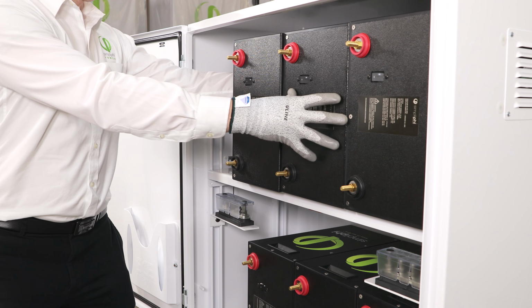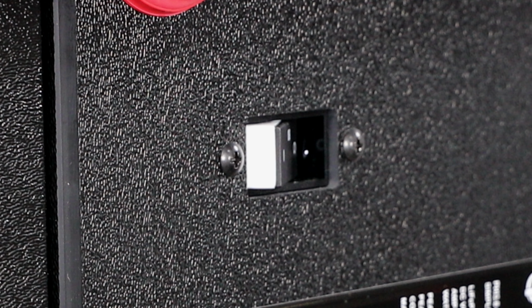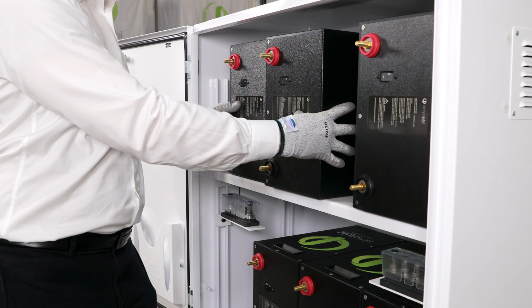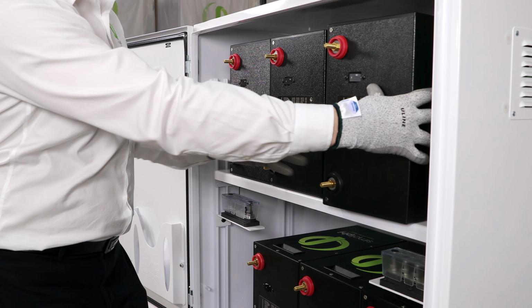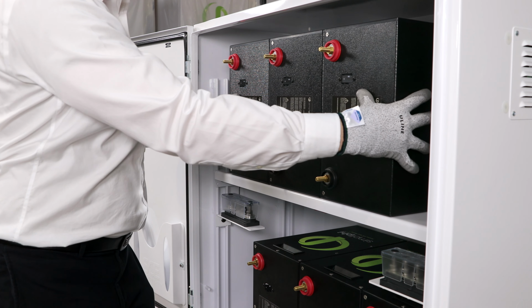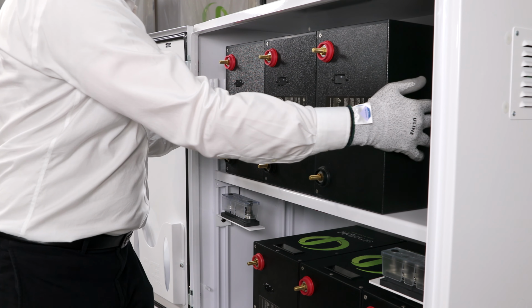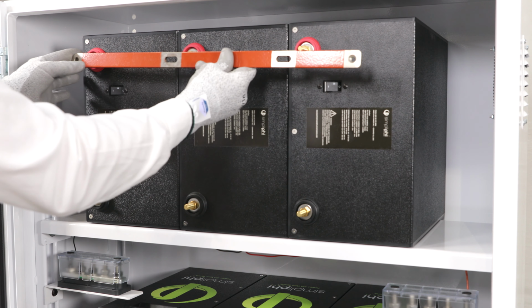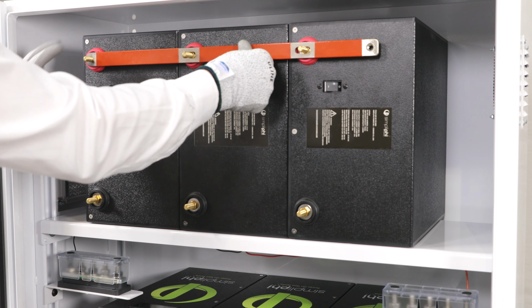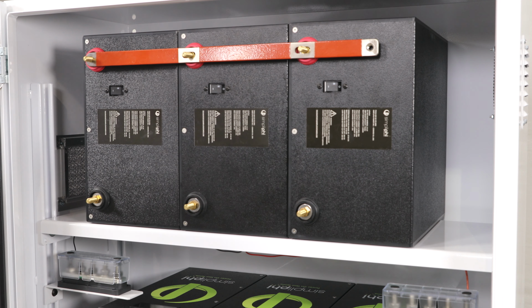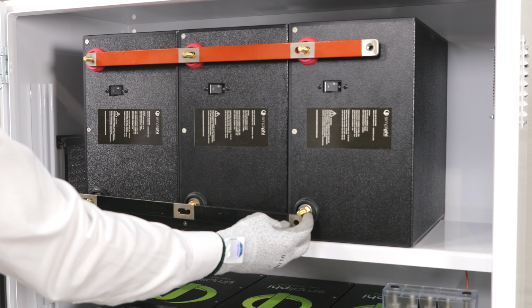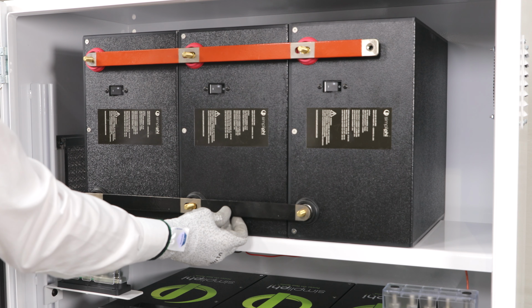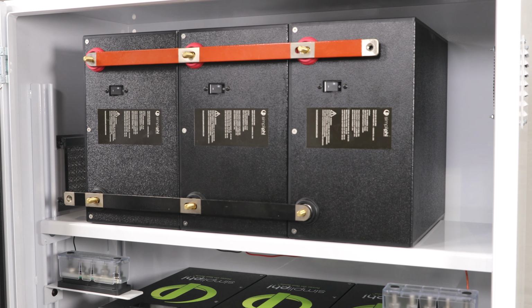Once all batteries are in the enclosure, confirm that all the battery module circuit breakers are still in the off position. Before placing the bus bars on the batteries, position the batteries so that they are centered on the shelf and positioned directly next to one another. Place the bus bars across the battery terminals. Arrange the bus bars so that the cable landings are opposite one another, and the threaded cable mounting on the bus bar faces towards the battery.